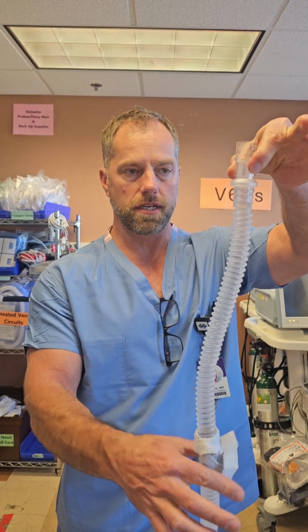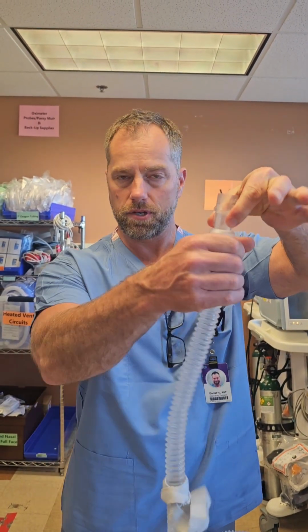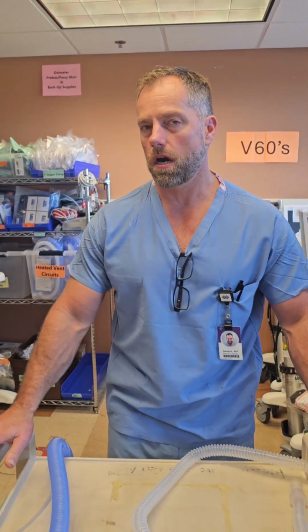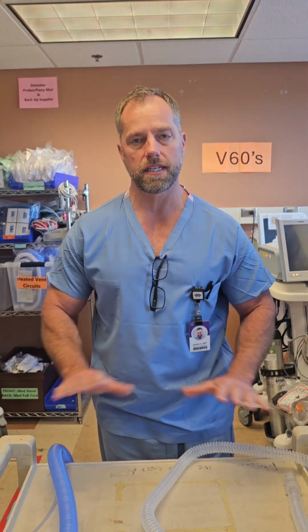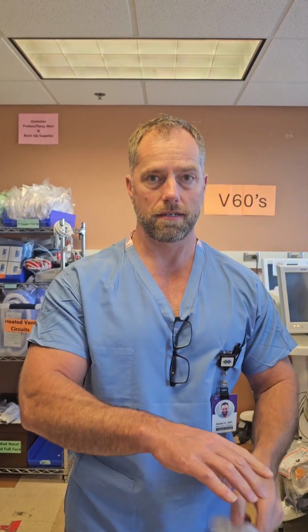If you're using this, we get rid of the tubing and put the heated circuit here, maintaining the exhalation valve. The key point is to maintain the exhalation valve when you put a heated circuit on. If you don't understand what you're doing, please don't attempt to do this. With that, good luck.